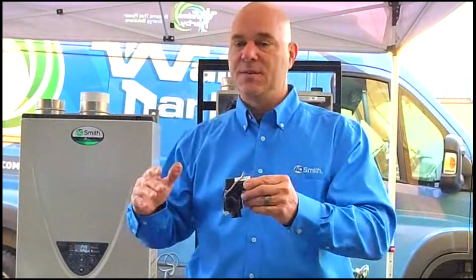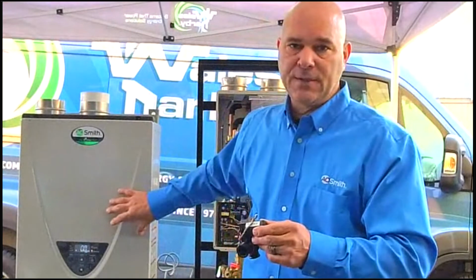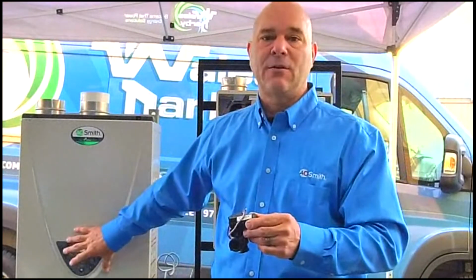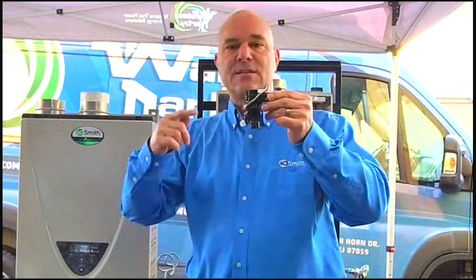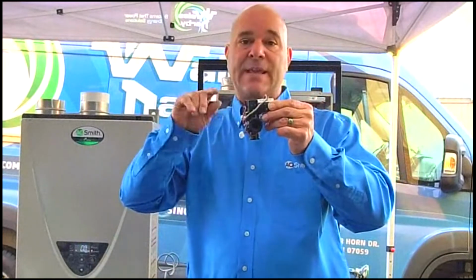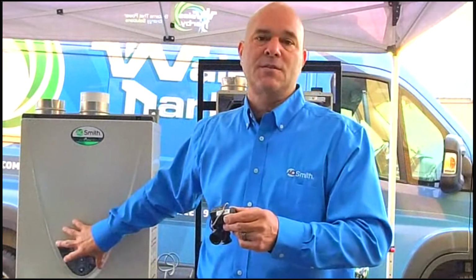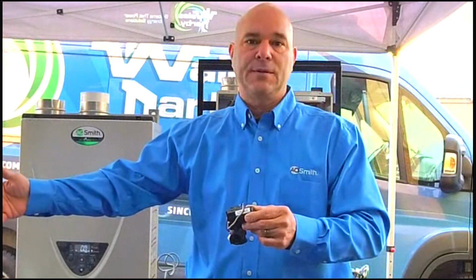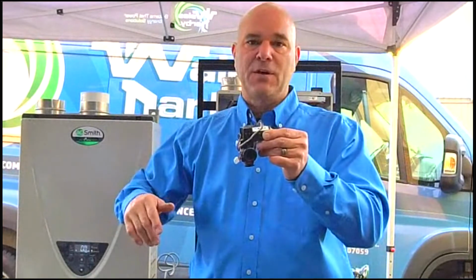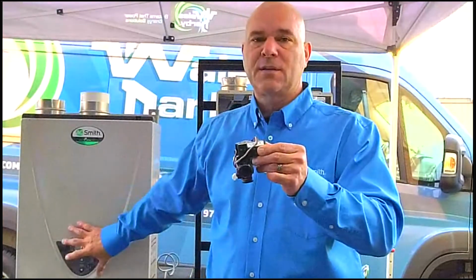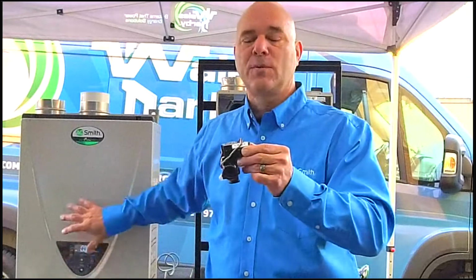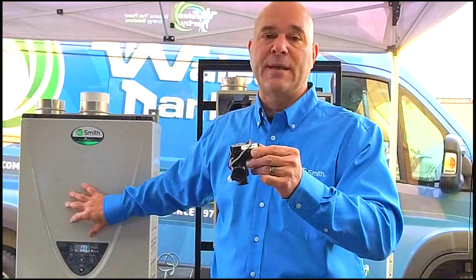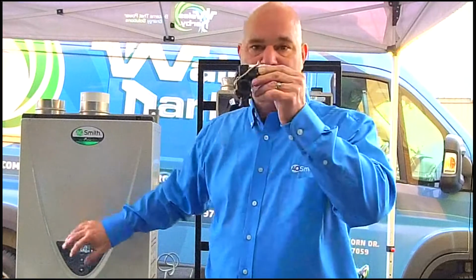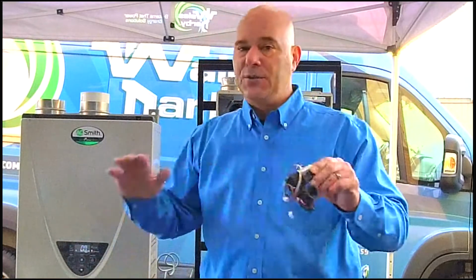Okay, I'm going to say that again, because a lot of guys find it confusing. They know there's water going through the unit, but the unit's not firing and there's no error code. If this does not rotate, or it's rotating and not counting how many times it's rotating, the unit doesn't know there's water flowing across it. So the unit cannot give you an error code. The job of the flow switch is to register flow and let the control board know what the flow is. The control board will then decide what BTU input we need to run at to support that demand. So that's the job of the flow switch. No error code, unit not running.